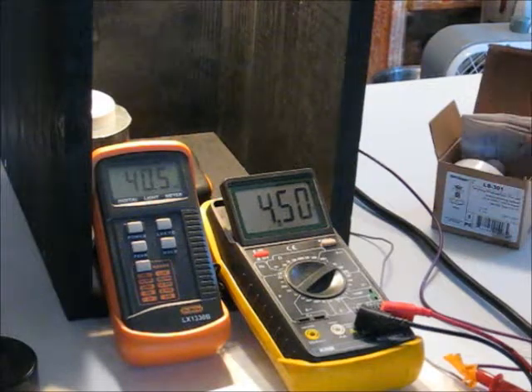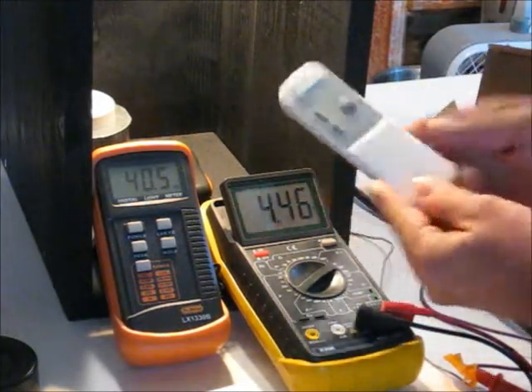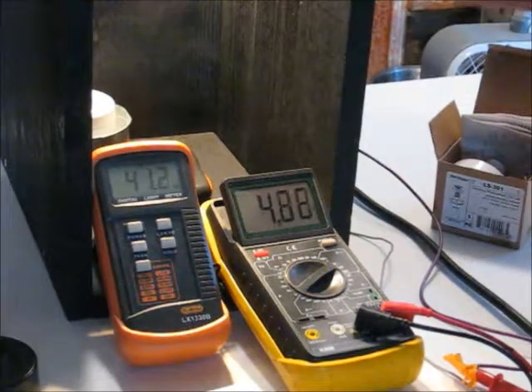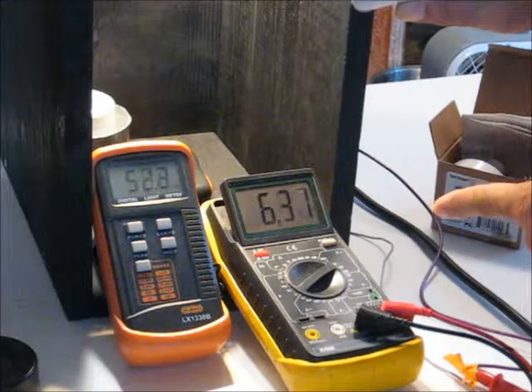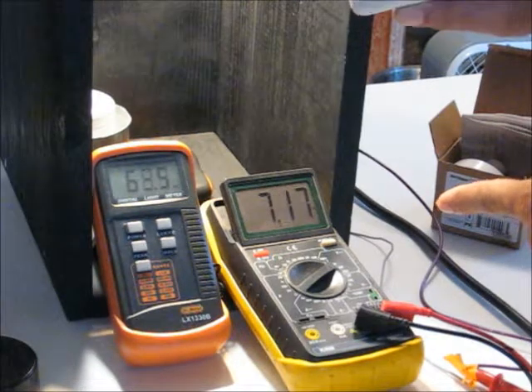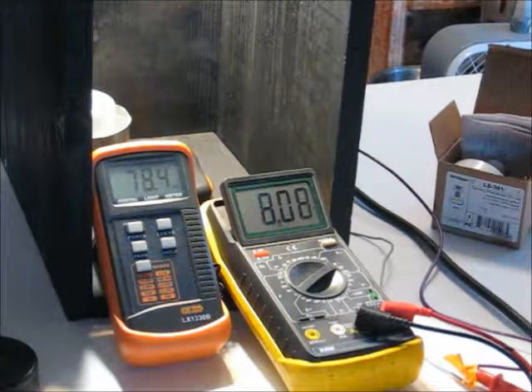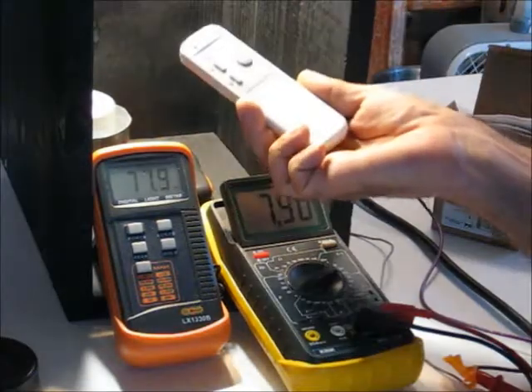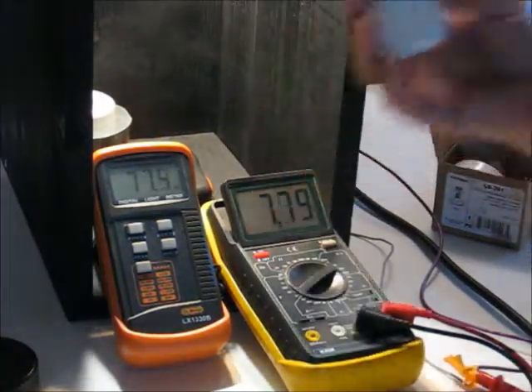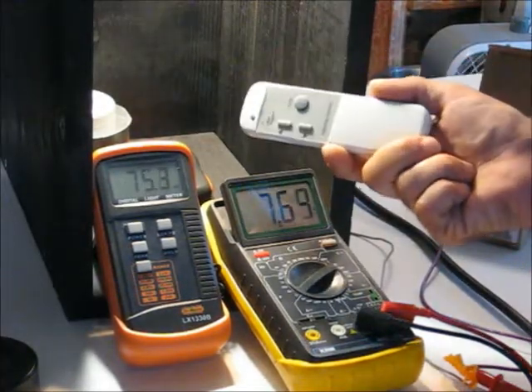Okay. The question is, can we take it above the daylighting set point using this control? So I'm just going to hit the up arrow. I'm at 5 volts. 6 volts, 7 volts, 8 volts, good enough. So we can override the daylighting set point using this multi-level control. Does this violate acceptance testing?